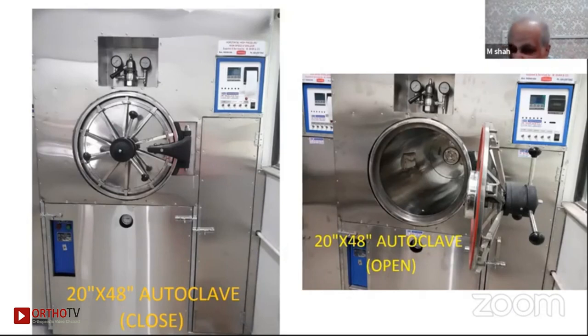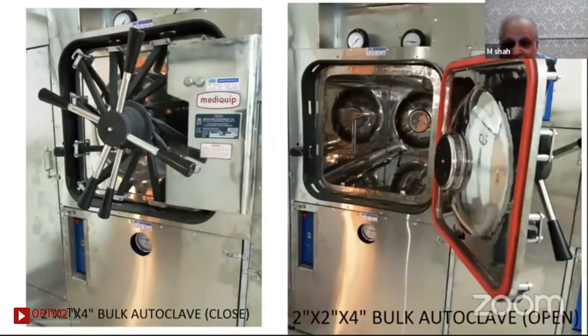32 psi. Now for 32 psi pressure, what is the thickness, what is the thickness of the jacket, how much kilowatt does it need, and how much is the exposure time, maybe 7 minutes, 3 minutes, 10 minutes, because at 121 you need about 20 to 30 minutes. So people started coming down and experimented, and ultimately we came with a high vacuum, high speed sterilizer, which is in vogue from the 1980s. The advantage is that the sterilization is 100% and faster. And what is the stainless steel etcetera to be used?